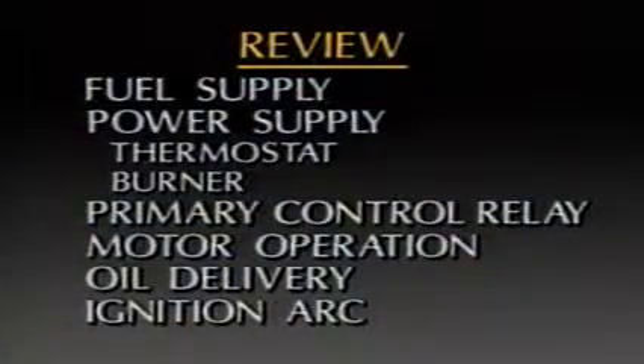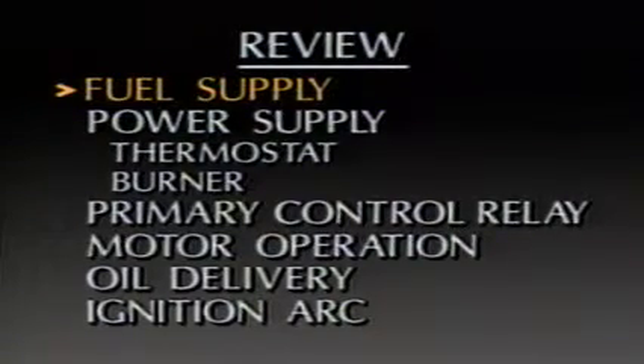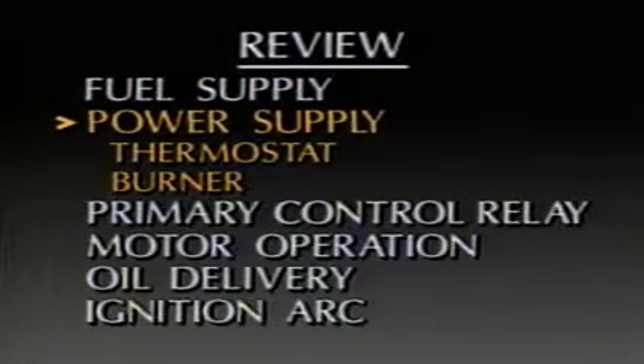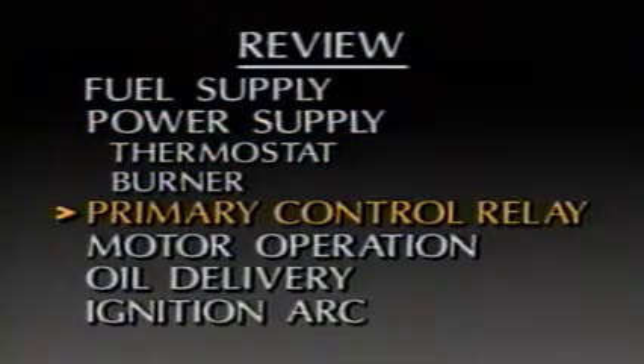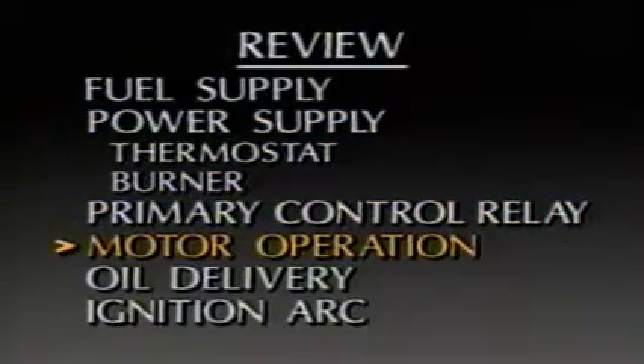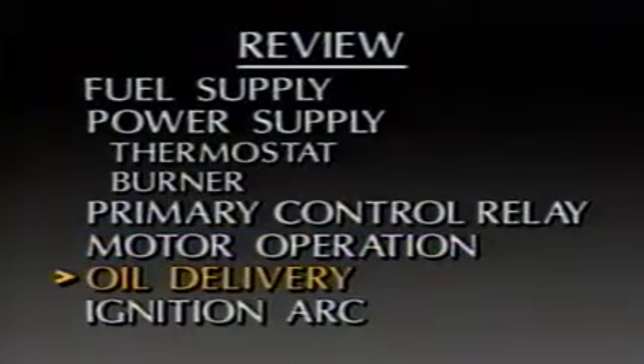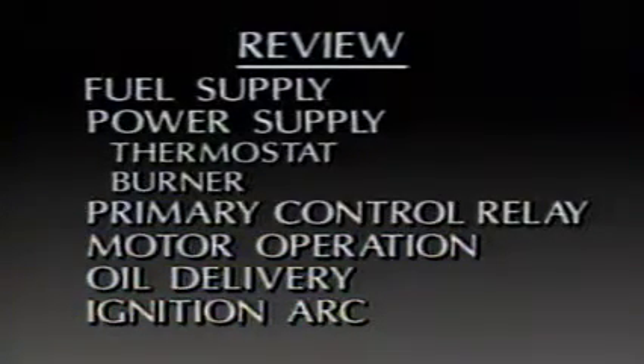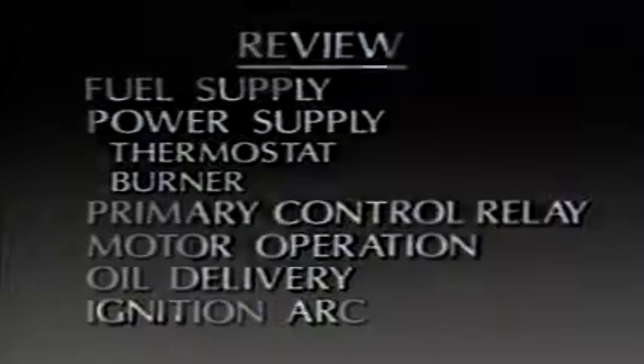Let's review the steps we've described so far. You've checked the fuel supply line, the power supply line, both at the thermostat and at the burner, the primary control relay, motor operation, oil delivery, and ignition arc. In most instances, these simplified steps will lead you to the source of the no-heat problem. However, if you still have not found the cause, you'll have to look deeper into the system. This calls for a careful check of the burner performance during the fire test.